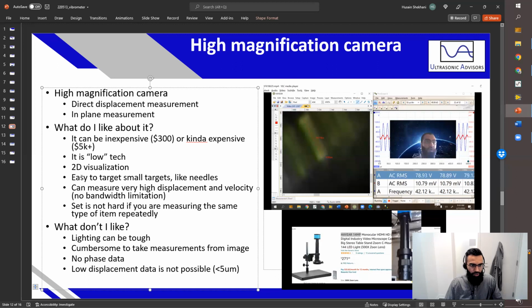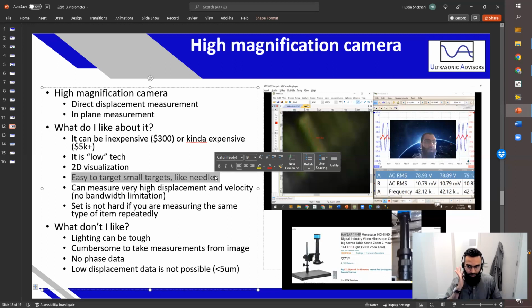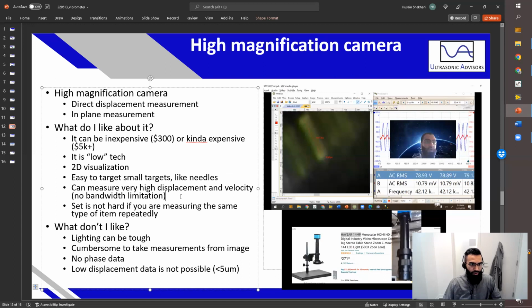So you can easily measure small targets. It's already a microscope built in. And you can measure very high displacement and velocity, and there's no bandwidth limitation. So it's not bandwidth limited, but it is displacement limited. There has to be, at least from my experience, over 5 microns of displacement, or you cannot make a measurement at all. You can't drive your transducer with 1 volt and expect to measure anything except what you started with. So you have to use a higher voltage, which is kind of nice because it forces you to characterize your device with a voltage in an environment where you'd actually be using it.